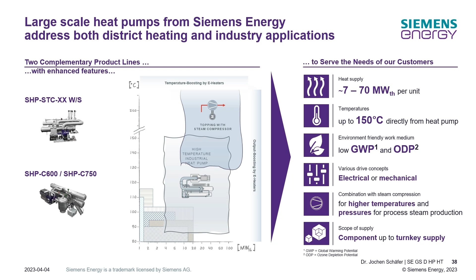We have the option to drive these heat pumps with an electrical drive, but in some special industrial applications we also think about mechanical drives, using a steam turbine to drive the heat pump compressor. This gives us the option to increase pressure and temperature for industrial applications, up to 55 bars and 270 degrees C. We would be willing to do a component supply, something like a heat pump island, or even a full turnkey solution if the application is large enough.